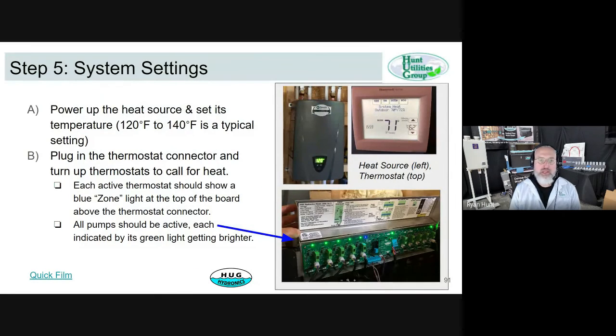All right, now the loops are full. You do that also for the boiler, just make sure it's full. And then you can get on to the other system settings and start up. You want to set the boiler temperature. 120 or 140 is typical, but it'll depend on what type of floor you're feeding.